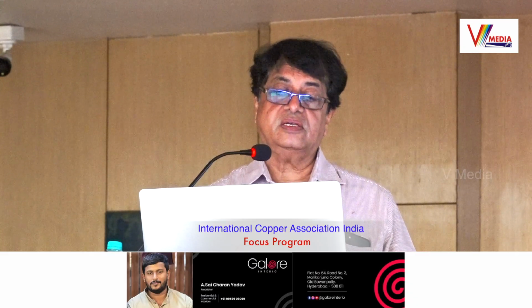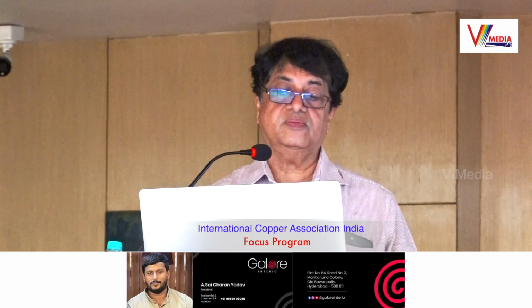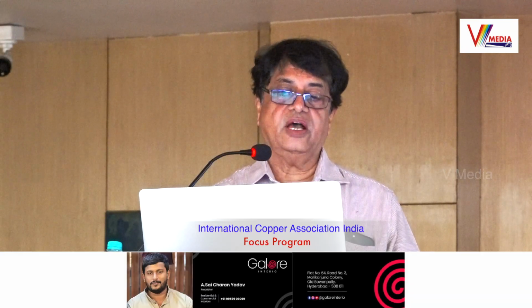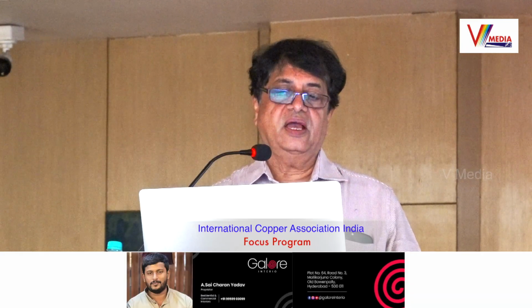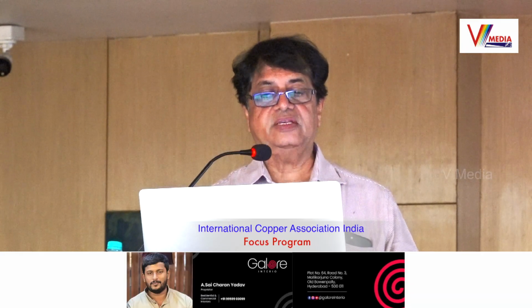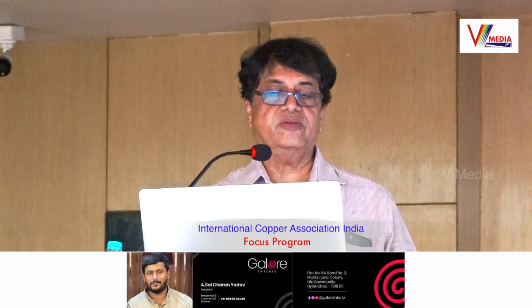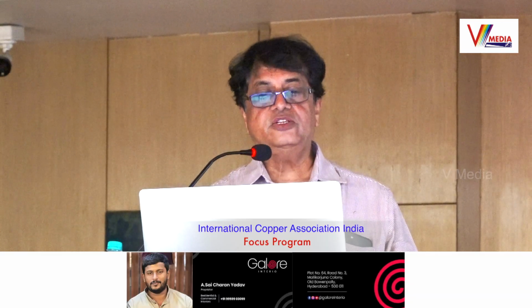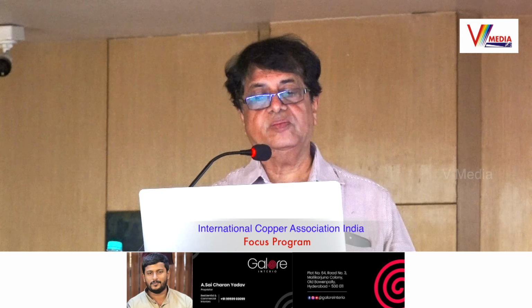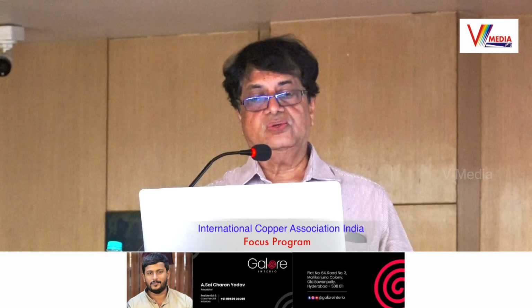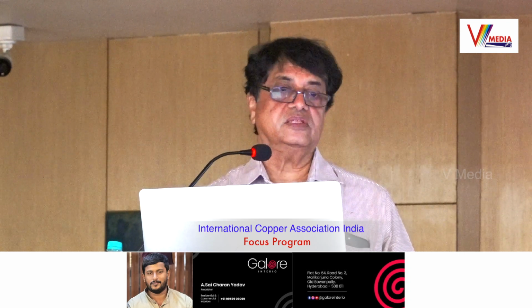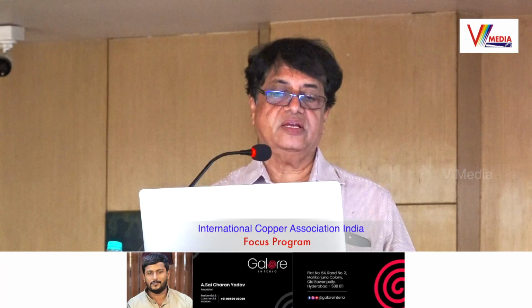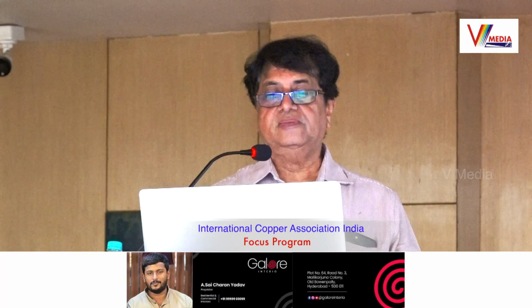Suppose he carries out the false ceiling for his existing ceiling. The height between the fan blades and the ceiling becomes less, and this creates a negative pressure between these two. This negative pressure leads to heating of the motor, and the motor may give way. So this is not correct. Again, this part relates to the planning of electric installation in your interior design.